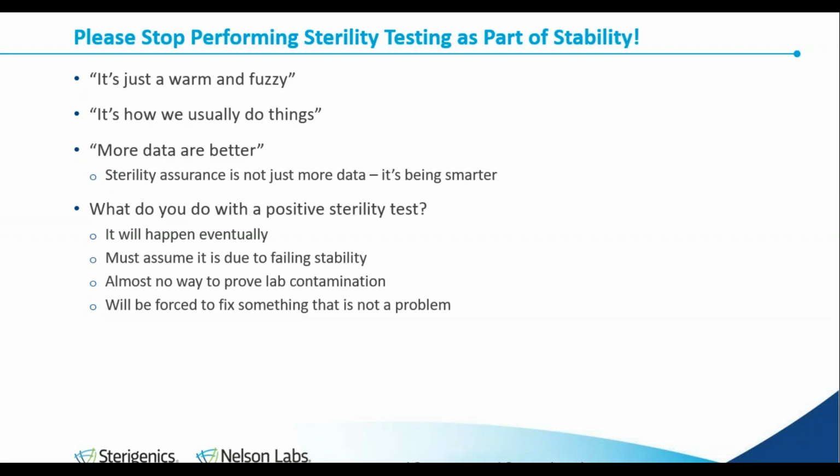So you're left with this thing to have to deal with, and you'll be forced into taking action for something that really is not a problem. So that's my plea to the industry to think very carefully. Really, the purpose for sterility testing of a product is only in development and maintenance of a sterilization process, not as part of stability evaluation or as part of routine lot release.